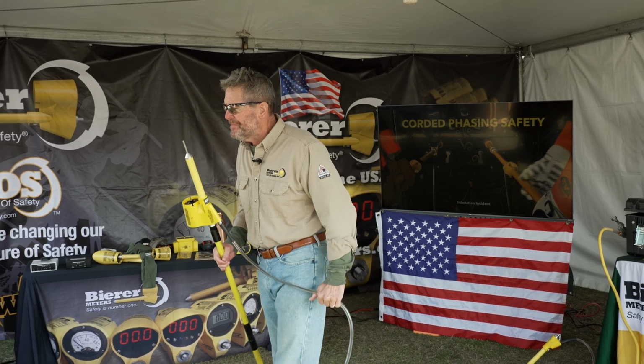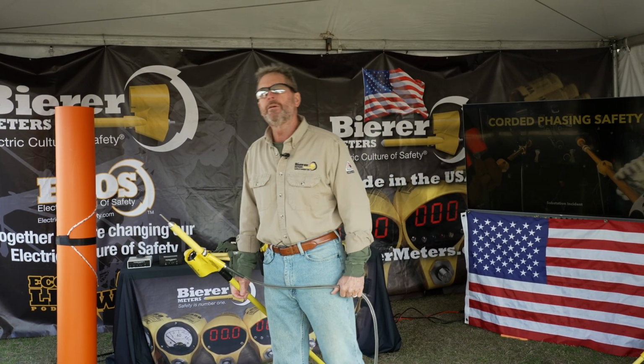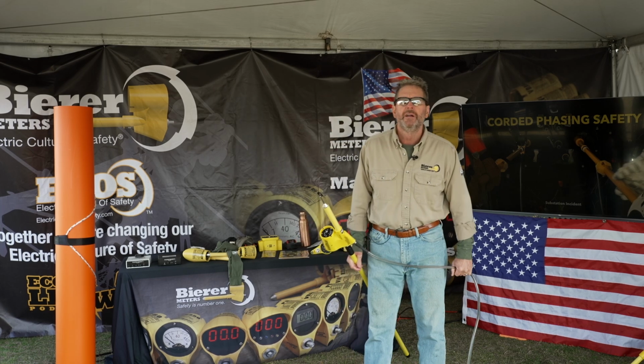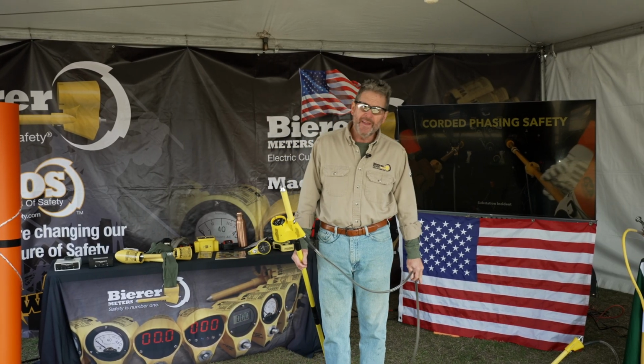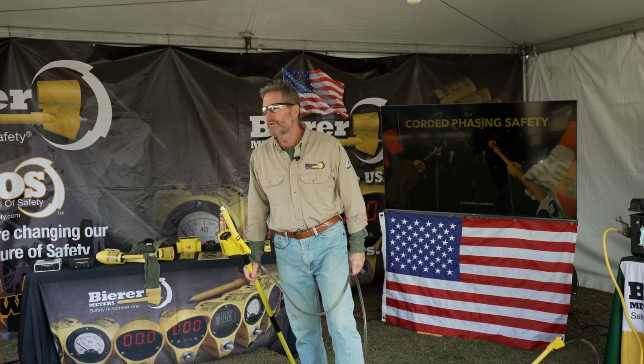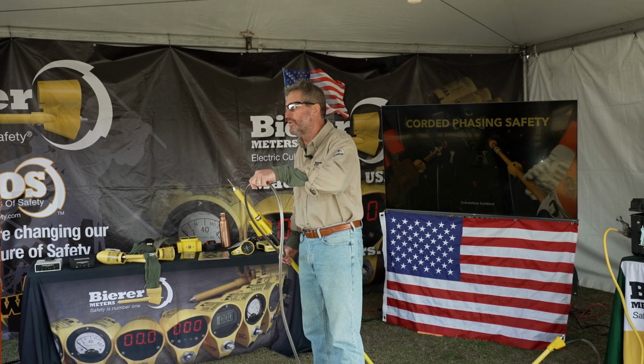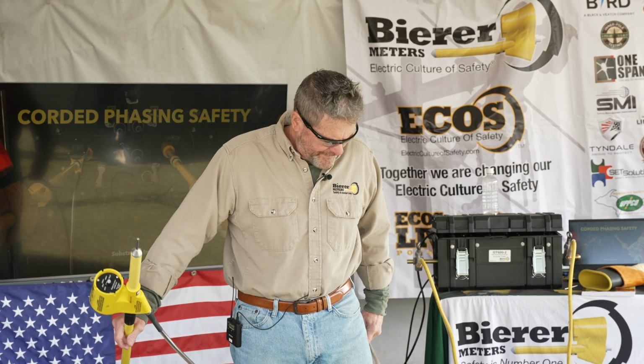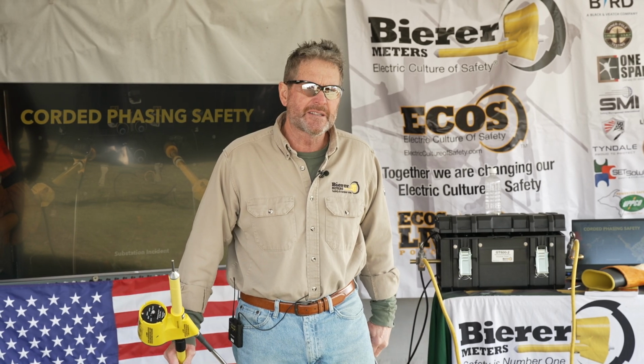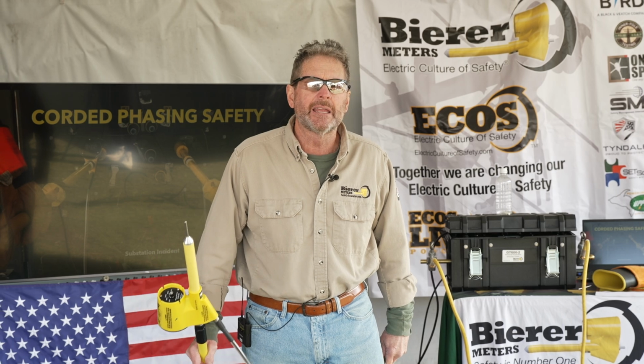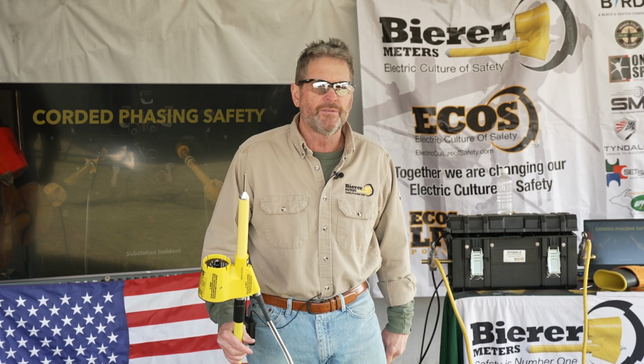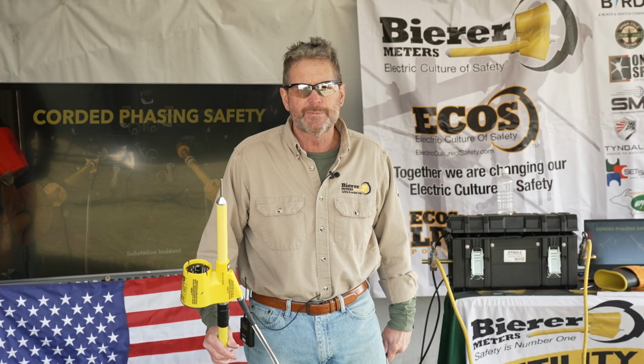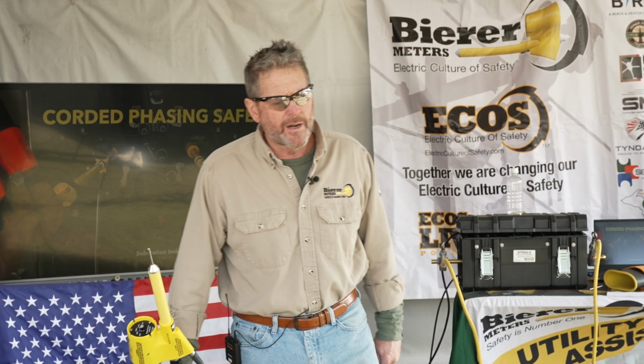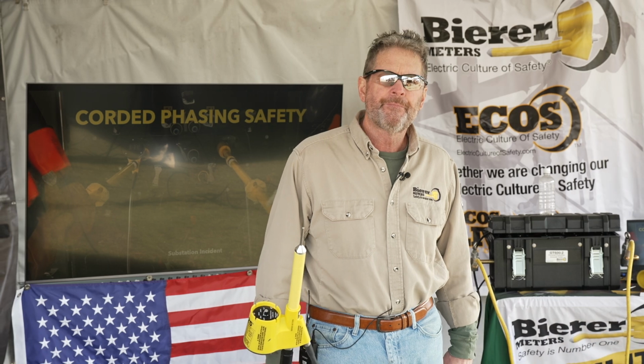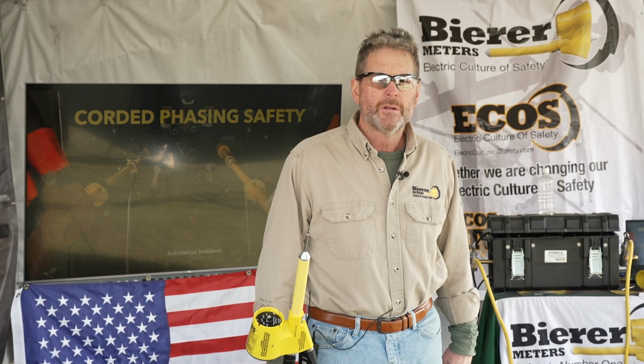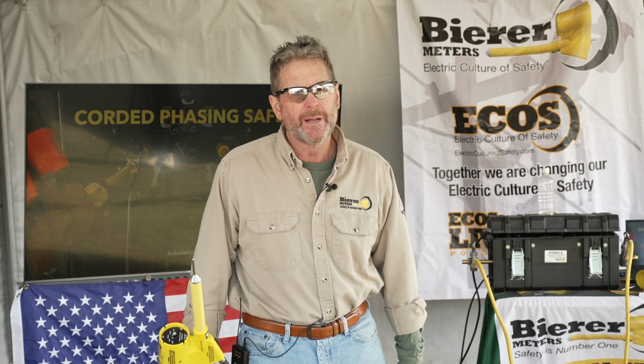So anyways, what if when they were using that tool, what if they did not train? Think about this - their line workers were supposed to stay away from that cord 36 inches. What if that cord, when they were using it going phase to ground, what if that cord was leaning against something when that full potential blew up and flowed through that cord lickety split? What if that cord was next to one of those linemen's thighs? You've heard of step potential? The higher potential's over here, but it's lower on this leg.